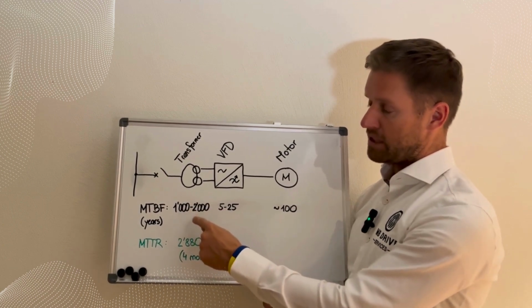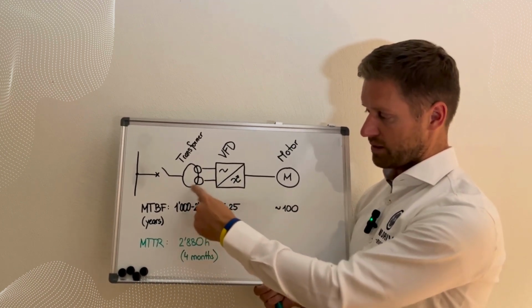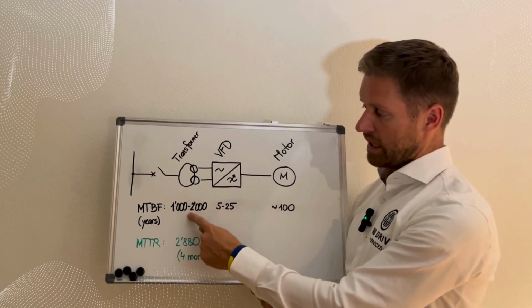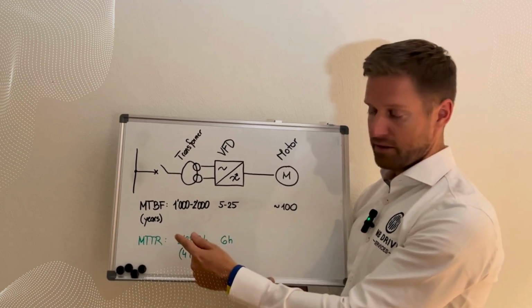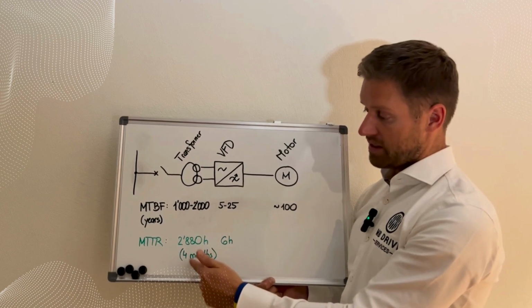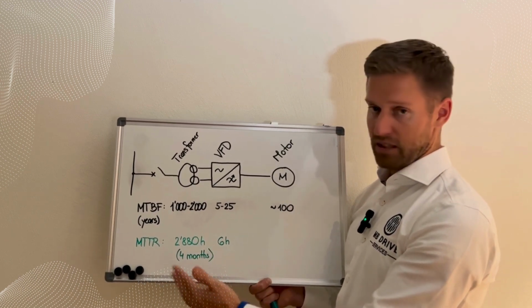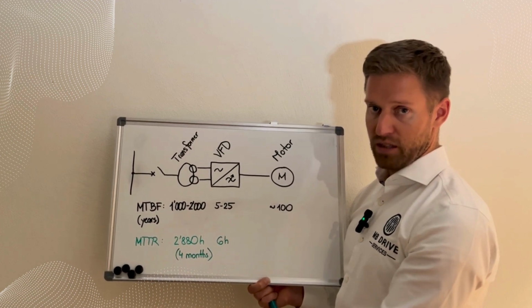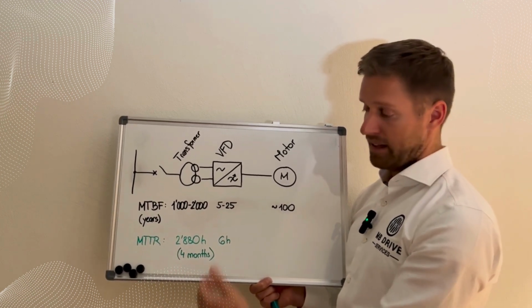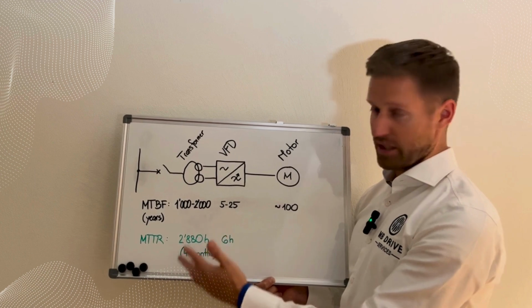Whereas the VFD, the transformer has a very low probability of a failure, but if it happens, it has very severe impact. You can have really very long unplanned downtime, and this might be a risk for the operation.